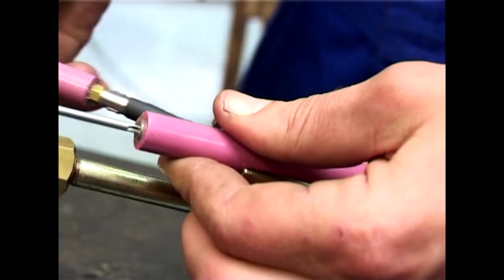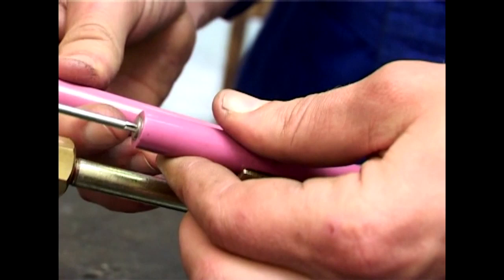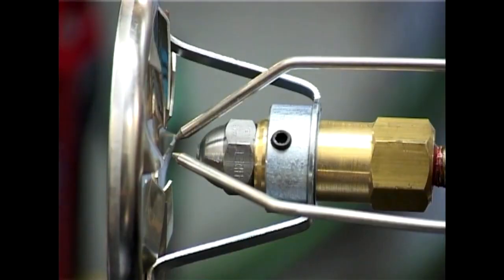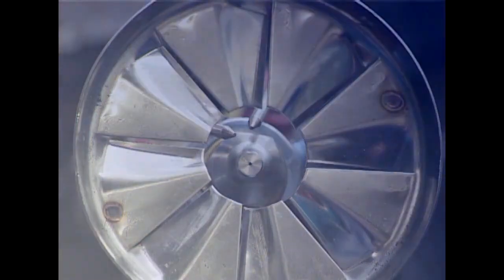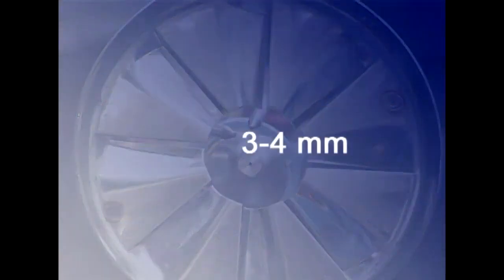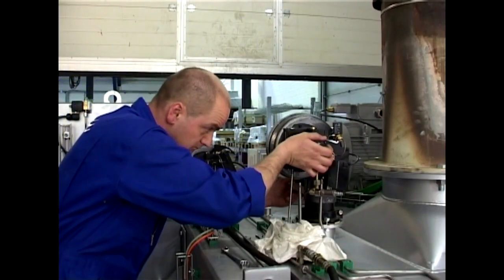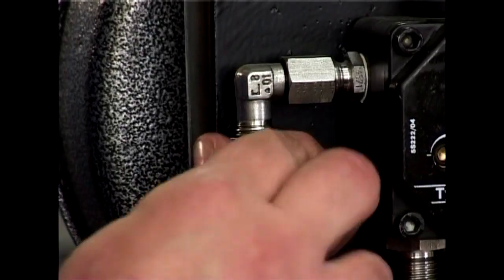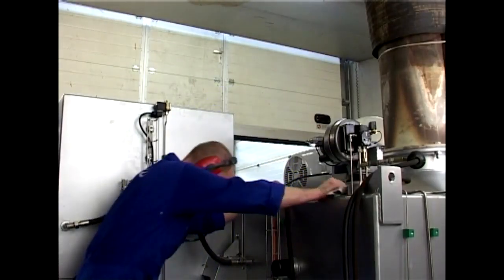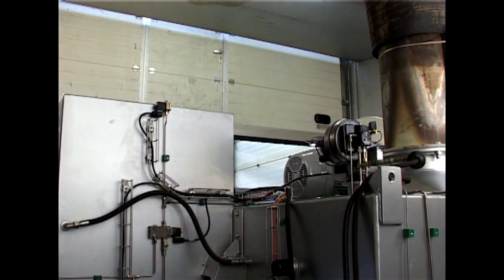Before you assemble the burner again, remember to adjust the electrodes. The tips of the electrodes should be approximately 9.5 mm from the center of the diesel oil nozzle, and the distance between the tips should be approximately 3 to 4 mm. Finally, assemble the burner and reinstall it. This routine should be carried out for every 2,000 hours of operation.